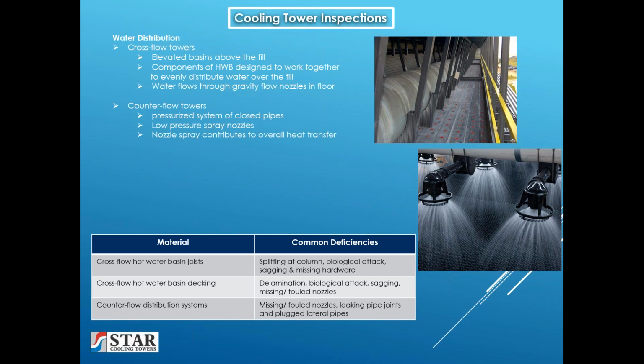Counterflow towers utilize a pressurized system of closed pipes. We have a header pipe and laterals in each individual cell. The low pressure spray nozzles provide even and equal distribution over the packing. And this nozzle spray actually contributes to the overall heat transfer.